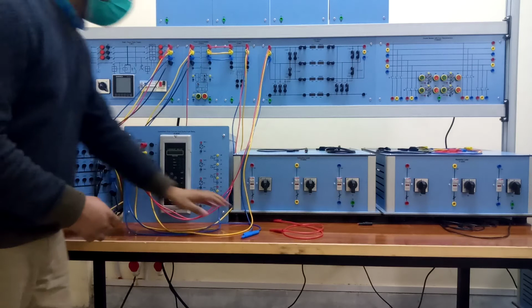So here you go, these three phases are now connected with your supply. Hiding the wires a bit so you get a good overview of the connections. Now we've connected the power supply to the power circuit breaker, the power supply to the three-phase transformer, and the output of this transformer is connected to the power circuit breaker, which goes to the summation current transformer. From the summation current transformer, this connection goes to the combined overcurrent and earth fault relay, and the output is then going to the line model.